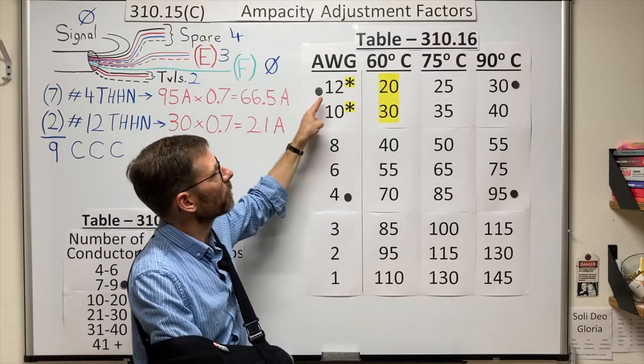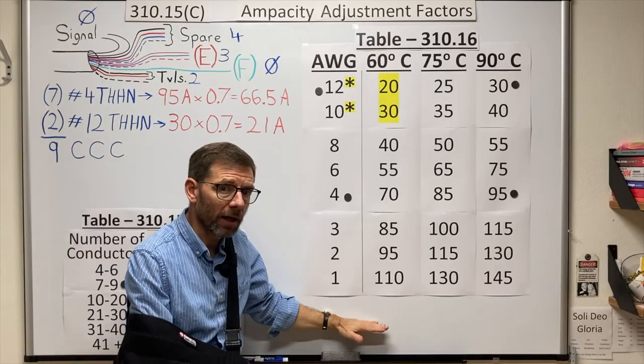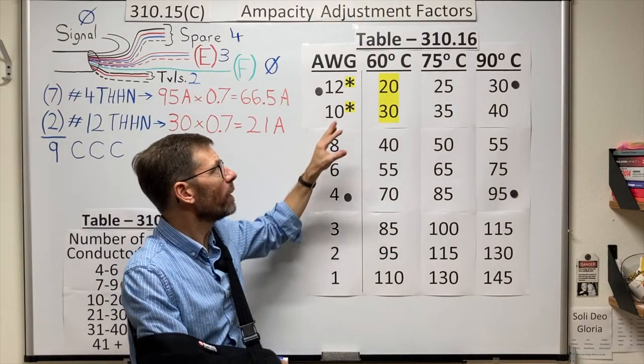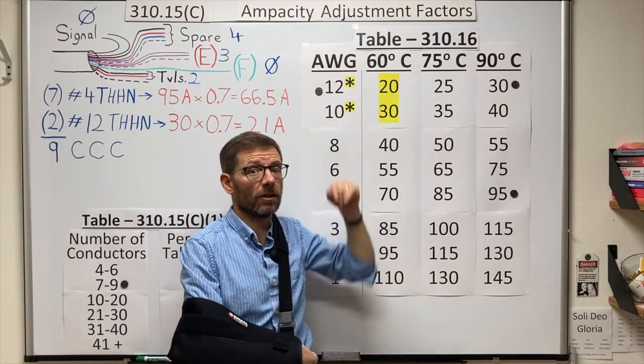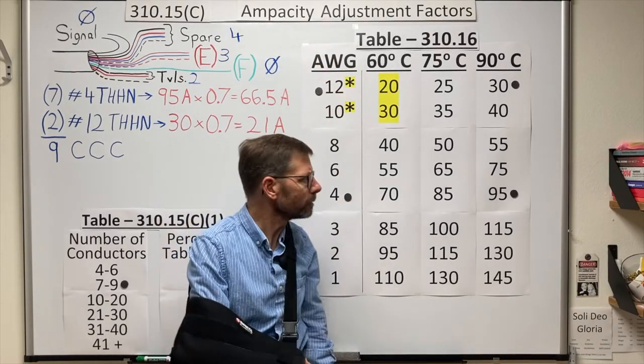But I also picked number 12 just to remind us of the asterisk here that explains where to go at the bottom of the table. Always double check your small conductor rules if you're using number 10s, 12s, 14s, or smaller.